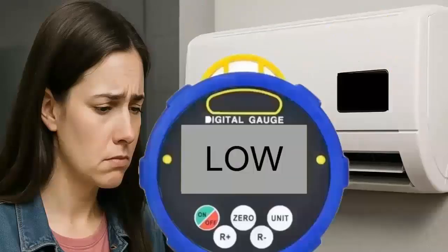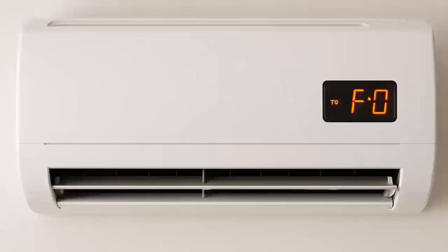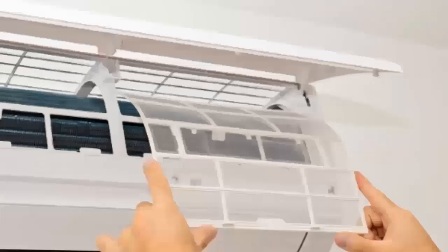D. Use gauges to measure the gas pressure. With R410A or R32, you should see around 118 psi. E. Some units low on refrigerant will show frost first on the indoor coil.